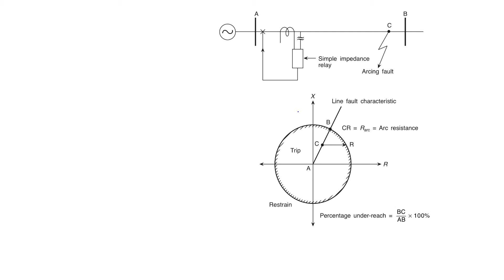So the simple impedance relay underreaches because of the arcing fault, and the percentage underreach is defined as the ratio of the distance by which the relay underreaches to the reach setting of the relay. It is given by BC, the distance by which the relay underreaches, divided by the reach setting of the relay, which in this case is AB, into 100. This is known as the percentage underreach of this relay. So from this we see that because of the arcing resistance, this relay is going to underreach.